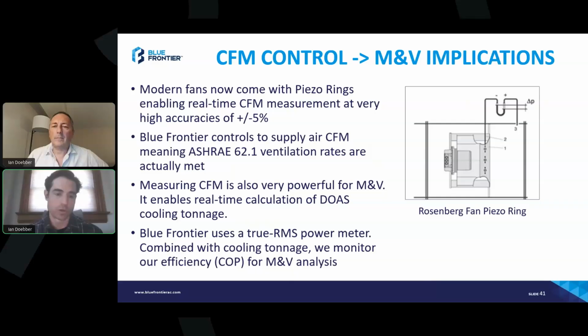We can always switch to static pressure control for conventional systems, which we are doing at a few sites, but we typically like to control CFM because that's what the customer cares about. You're providing ventilation to the building to meet ASHRAE 62.1 requirements. This also opens up another powerful aspect, which is M&V. Being able to measure CFM accurately to plus or minus 5% is the spec we've seen from Rosenberg and EBM-papst, although we've done comparisons to lab-grade nozzle flow measurements, and it's usually better than that, around 2 to 3% accurate.